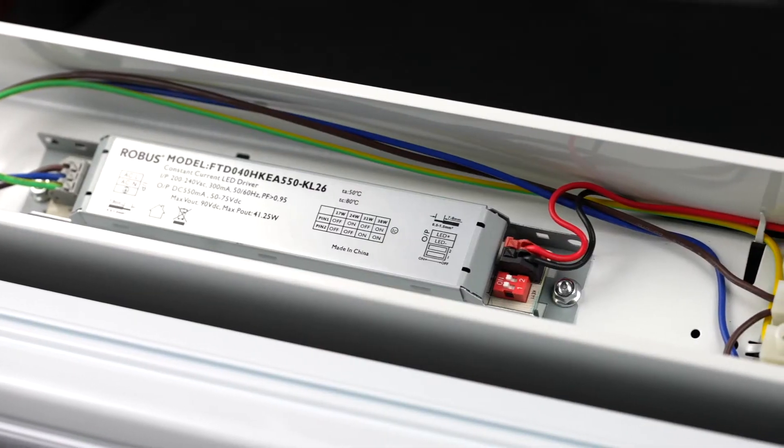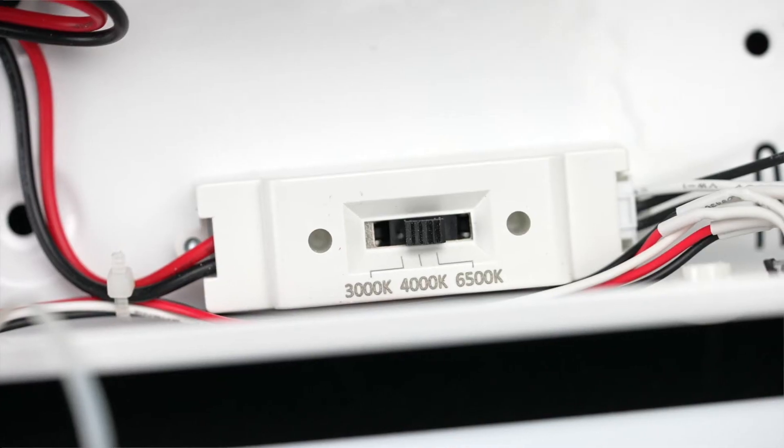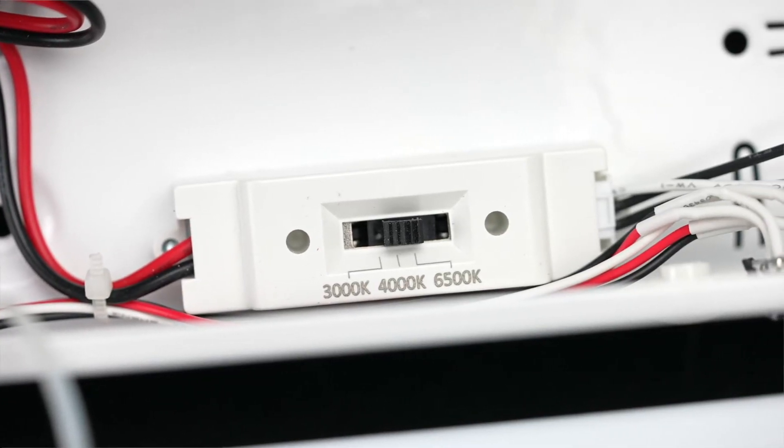A big key bonus: it's got four wattages — you can choose 16, 25, 32, and 40 watts, all in the one fitting. There's a little dip switch on the driver that you set, and all instructions are there so you can change the wattage to what you prefer. CCTs as per normal: 3000, 4000, and 6500 Kelvin.